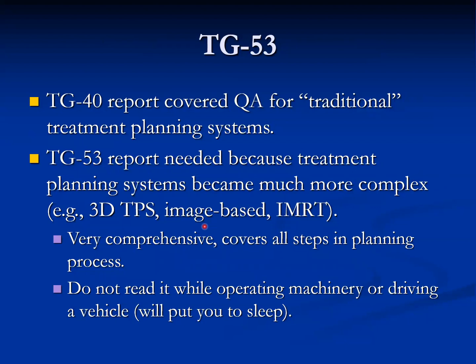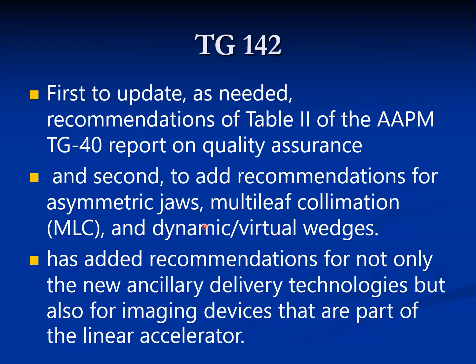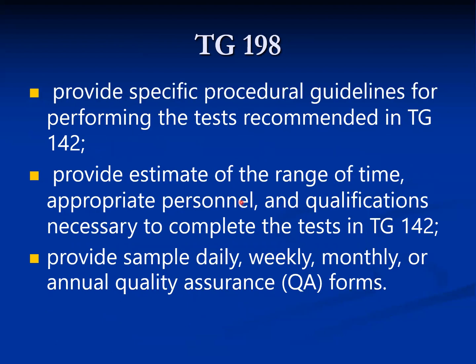The TG-53 report was needed because treatment planning systems became much more complex, and IMRT requires very comprehensive coverage of all steps in the planning process. The latest update is TG-142, which first updates the recommendations of Table 2 of AAPM TG-40, and second adds recommendations for asymmetric jaws, multi-leaf collimators, dynamic and virtual wedges, as well as new clarifications on technologies and imaging devices that are part of the linear accelerator. TG-198 provides specific procedural guidelines for performing the tests recommended in TG-142.